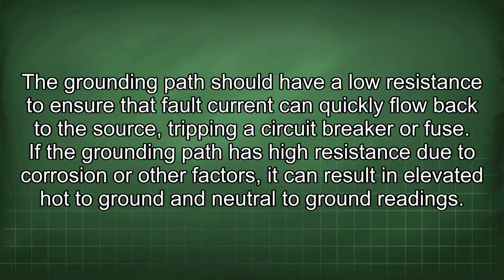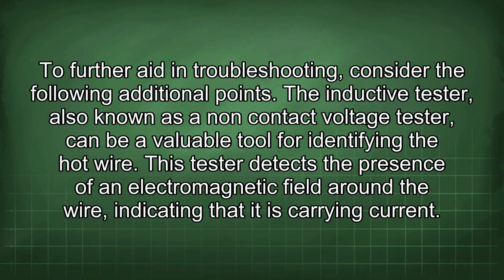The grounding path should have a low resistance to ensure that fault current can quickly flow back to the source, tripping a circuit breaker or fuse. If the grounding path has high resistance due to corrosion or other factors, it can result in elevated hot to ground and neutral to ground readings. To further aid in troubleshooting, consider the following additional points.